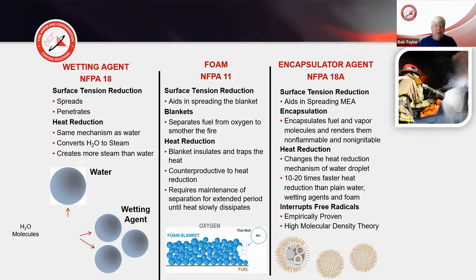NFPA 11 addresses foam. It talks a little bit about surface tension reduction, about getting a blanket of bubbles across a liquid or a surface to temporarily separate the fuel from the oxygen and smother the fire, provided that blanket doesn't get interrupted by somebody walking through it, a hose line, or whatever. Even on 3-dimensional fires, it doesn't work very well because you can't maintain that blanket very long.